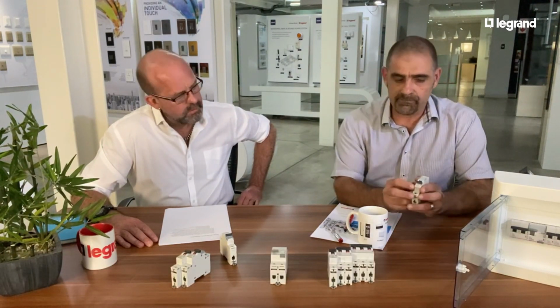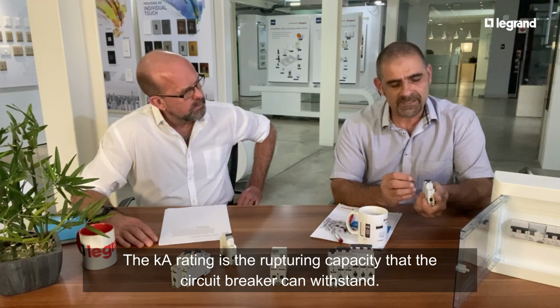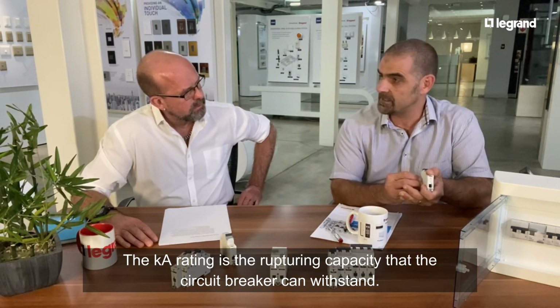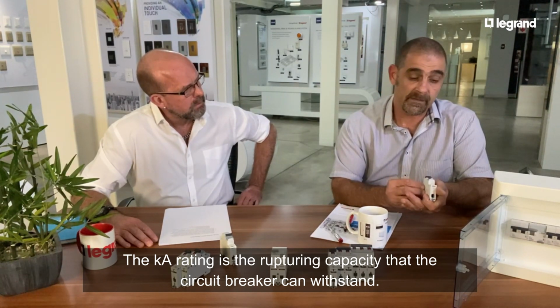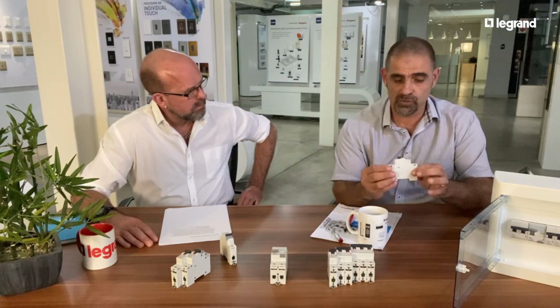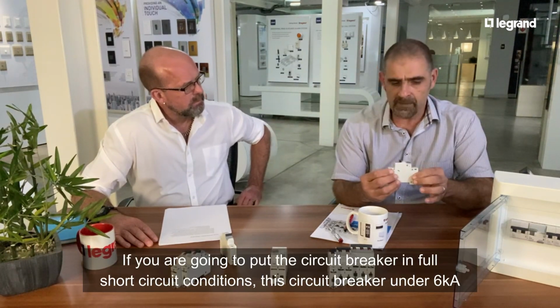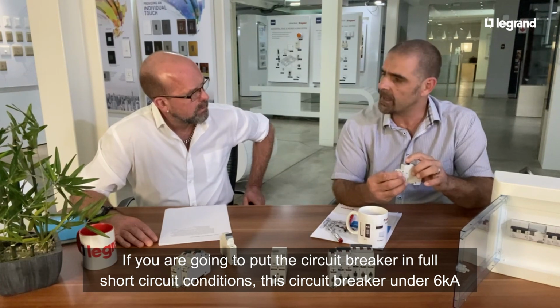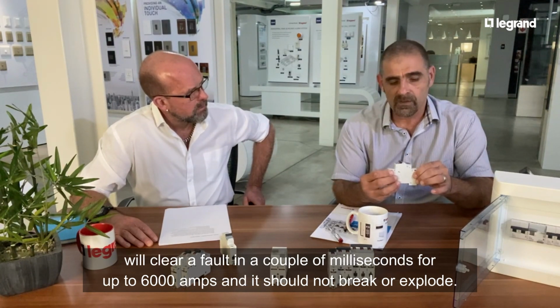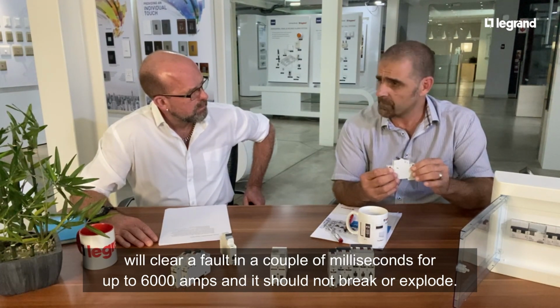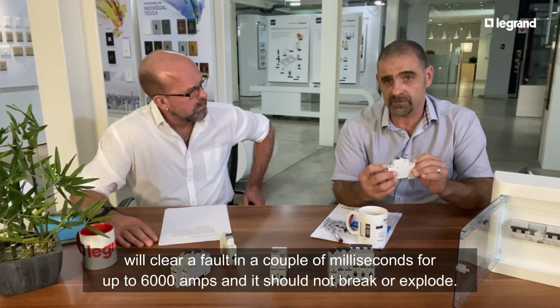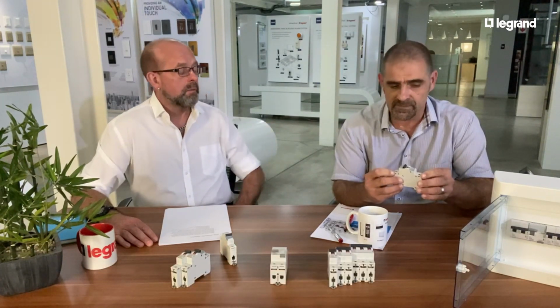The kA rating itself is the rupturing capacity that the circuit breaker can withstand if you're going to put this in full short circuit conditions. This circuit breaker, at 6 kA, will clear a fault for a couple of milliseconds at up to 6,000 amps. Wow. And it should not break or explode under that short circuit condition.